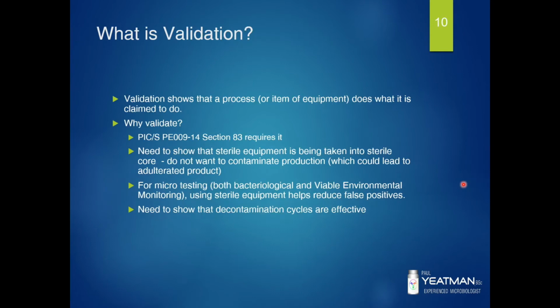What is validation? Well, validation shows that a process or item of equipment does what it is claimed to do. It's more critical for autoclaves used to support environmental monitoring than for media making or decontamination. For tasks such as media making, tests such as growth promotions or sterility testing will show up if media is substandard. Ensuring you use sterile equipment for microbiology tasks means there is less chance of you getting a positive result, and thus less chance of batches being placed on hold while action level investigation is conducted.